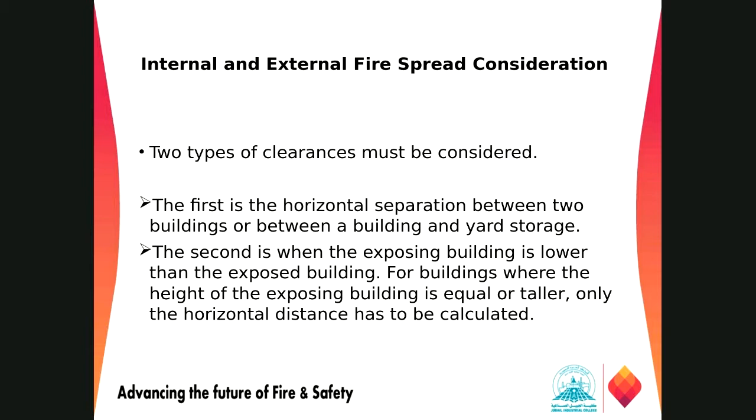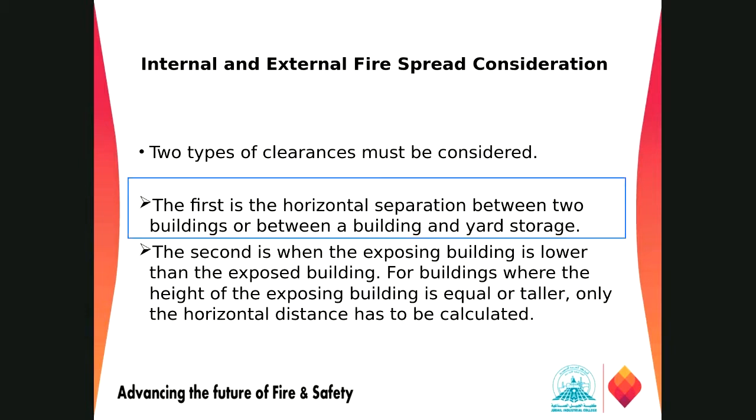While making internal and external fire plans, we have to take care of the adjacent buildings, if we are following the IFC code. So we have two types of clearance that must be considered. The first is the horizontal separation: what is the separation between two buildings, or between the yard storage and the building. The second is regarding the difference in the height of the buildings. When the exposing building is lower than the exposed building, the fire from the lower building will go higher and catch fire to the nearby building.